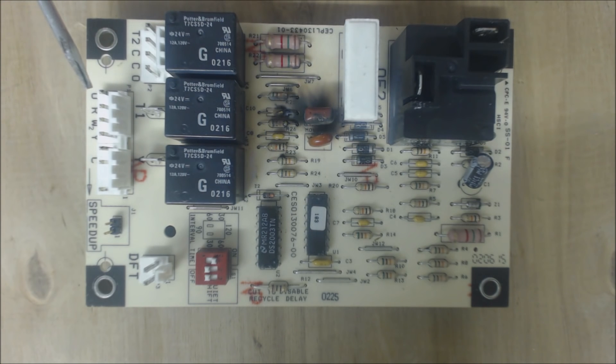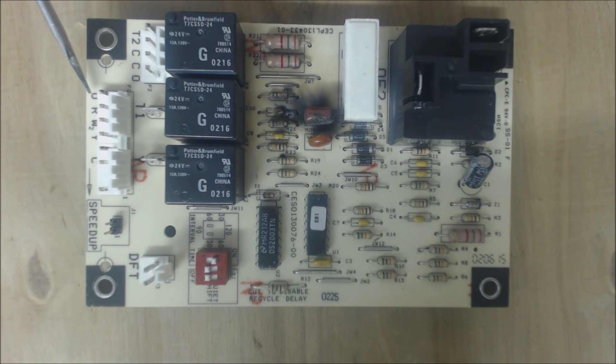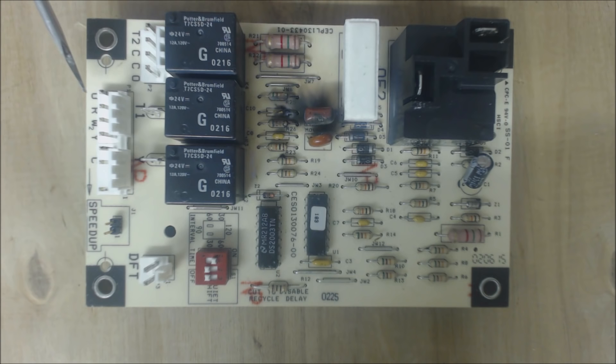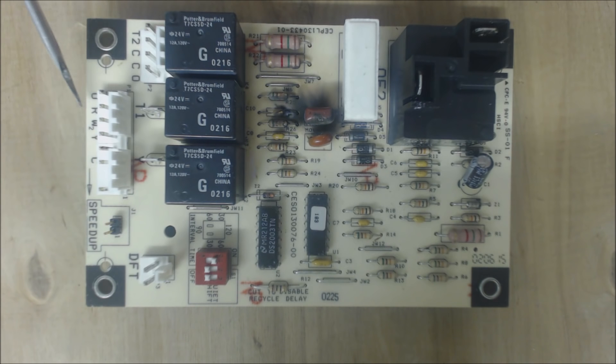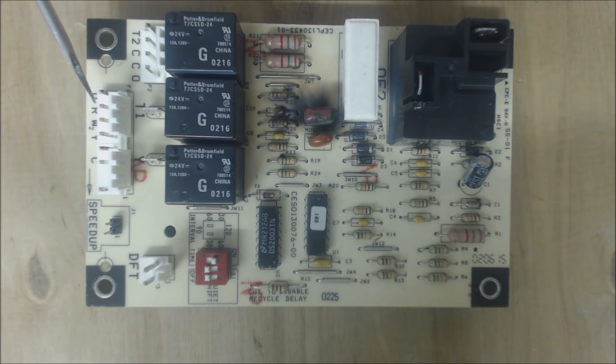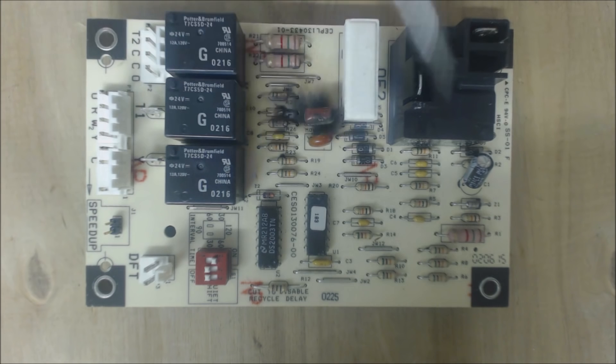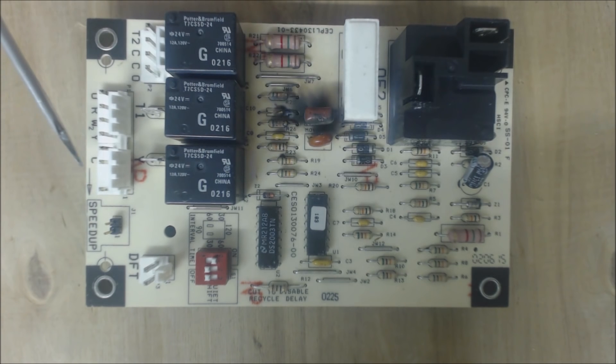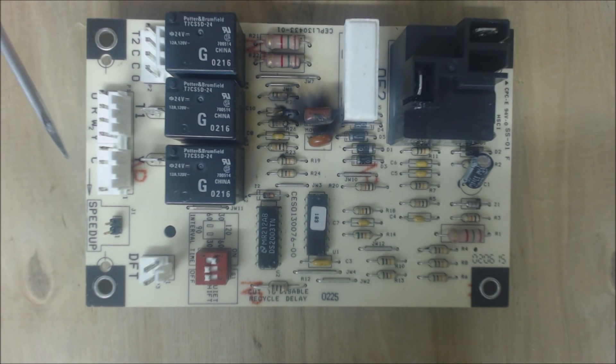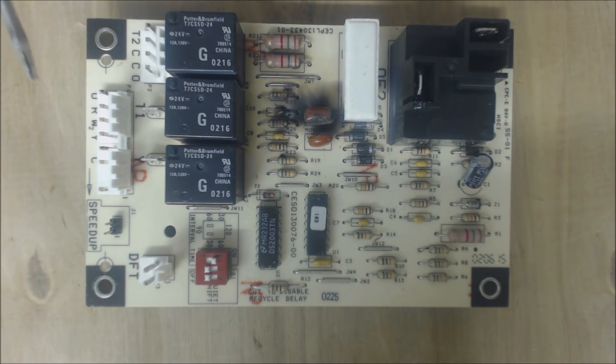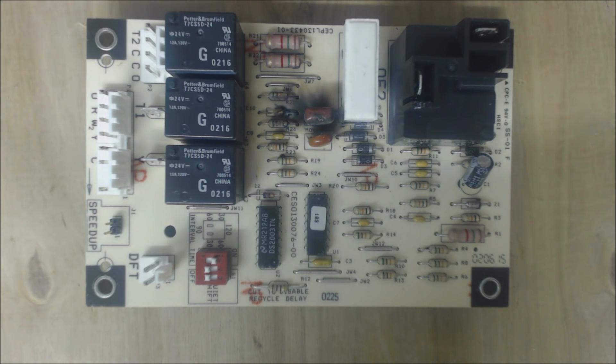So I'm going to go over everything. You have the O which comes in as the power to the reversing valve from the indoor unit. Then the R wire, the R terminal, comes in as 24 volt power, consistent 24 volt power to this control board. And then you have C where it comes back out of the control board, powering this load and going back to the indoor unit. So R is where it comes in, C is where it comes out, C is the common.